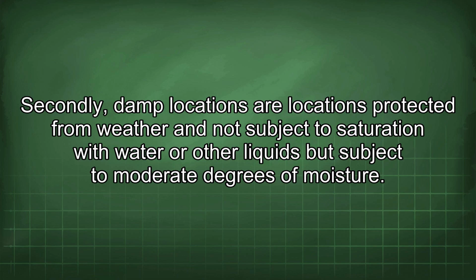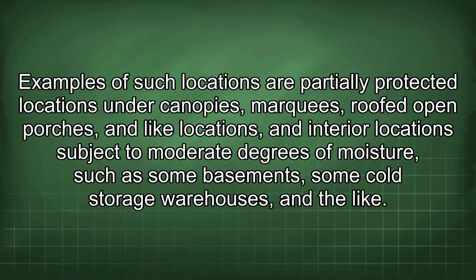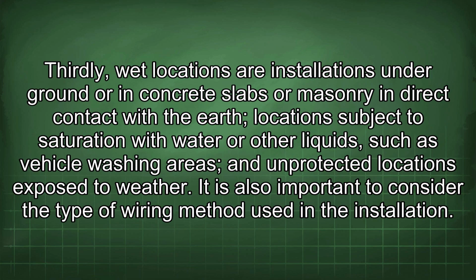Secondly, damp locations are locations protected from weather and not subject to saturation with water or other liquids but subject to moderate degrees of moisture. Examples of such locations are partially protected locations under canopies, marquees, roofed open porches, and interior locations subject to moderate degrees of moisture such as some basements, some cold storage warehouses, and the like. Thirdly, wet locations are installations underground or in concrete slabs or masonry in direct contact with the earth, locations subject to saturation with water or other liquids such as vehicle washing areas, and unprotected locations exposed to weather.